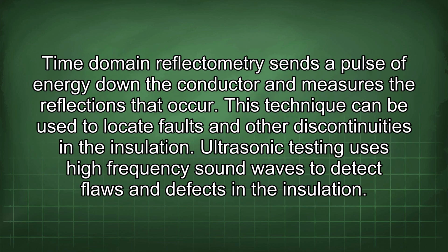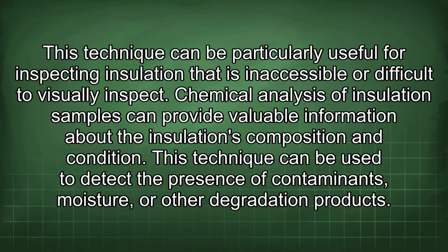Time domain reflectometry sends a pulse of energy down the conductor and measures the reflections that occur. This technique can be used to locate faults and other discontinuities in the insulation. Ultrasonic testing uses high-frequency sound waves to detect flaws and defects in the insulation. This technique can be particularly useful for inspecting insulation that is inaccessible or difficult to visually inspect. Chemical analysis of insulation samples can provide valuable information about the insulation's composition and condition. This technique can be used to detect the presence of contaminants, moisture, or other degradation products.